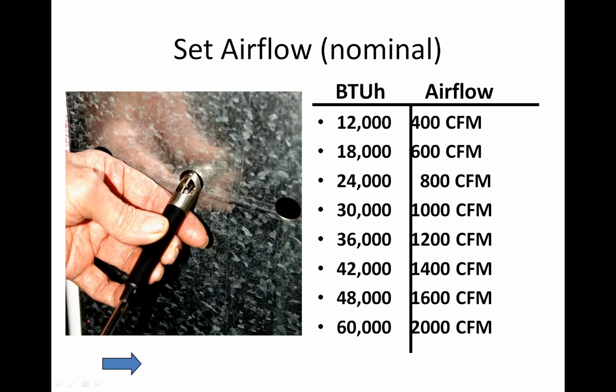But you'll find out with a lot of those manufacturers, it's operating at a lower airflow and a lower capacity, or it's a multiple stage compressor. Typically, all manufacturers operate at the same ratings, which is 400 CFM a ton, and that would be your full load or your full speed capacity.